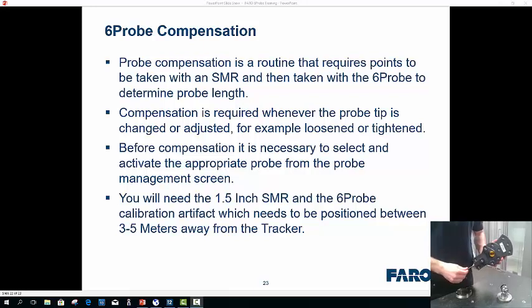Hello, in this video I'm going to show you how to compensate the 6Probe. Probe compensation is a routine that requires points to be taken with an SMR and then taken with a 6Probe to determine the probe length. Compensation is required whenever the probe tip is changed or adjusted, for example loosened or tightened.